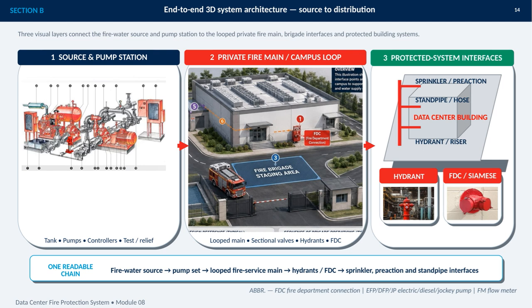The looped arrangement includes sectional valves, hydrants, and fire department connections, allowing the distribution network to serve multiple points while supporting isolation and access. The third layer is the set of protected system interfaces within the building. These include sprinkler and pre-action systems, standpipe and hose connections, and hydrant or riser interfaces. The external hydrant and FDC, or Siamese connection, provide visible brigade access points. So the readable sequence is straightforward: fire water source, pump set, looped fire service main, hydrants and FDCs, then the sprinkler, pre-action, and standpipe systems that protect the building.